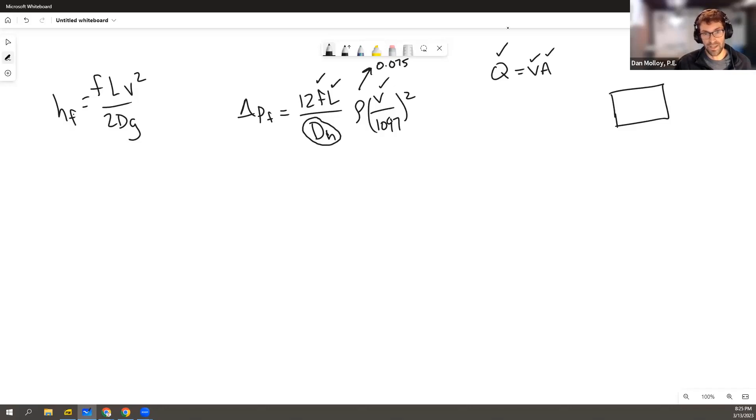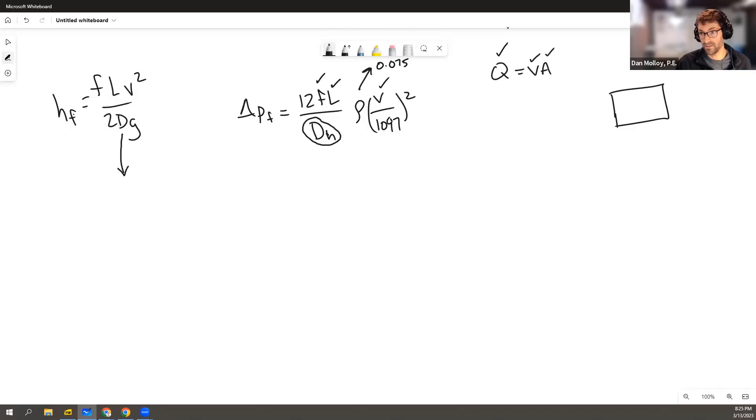In this, I made the assumption, which I thought was pretty reasonable in the solution, that the diameter, since it's not a circle, it's not a round duct, it's a square duct, should be DE, the equivalent diameter for a duct.